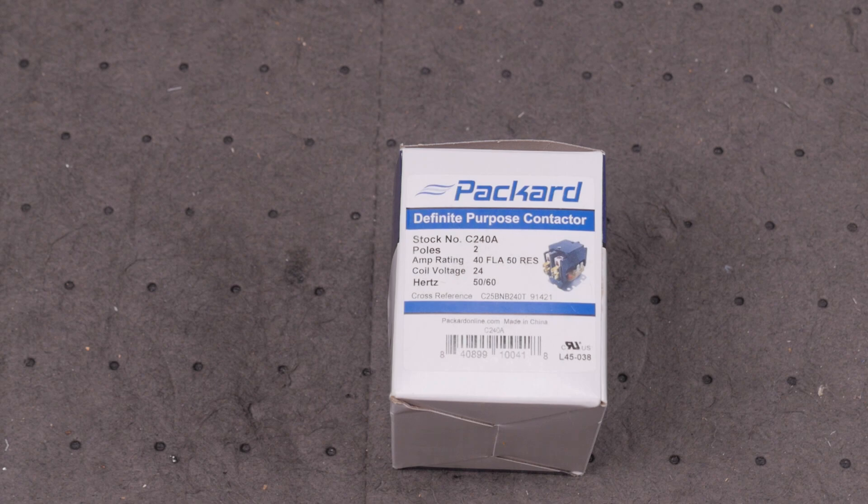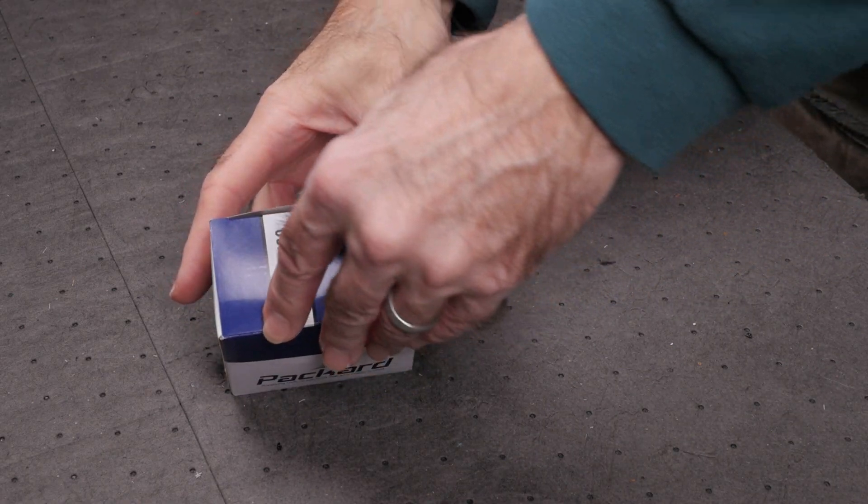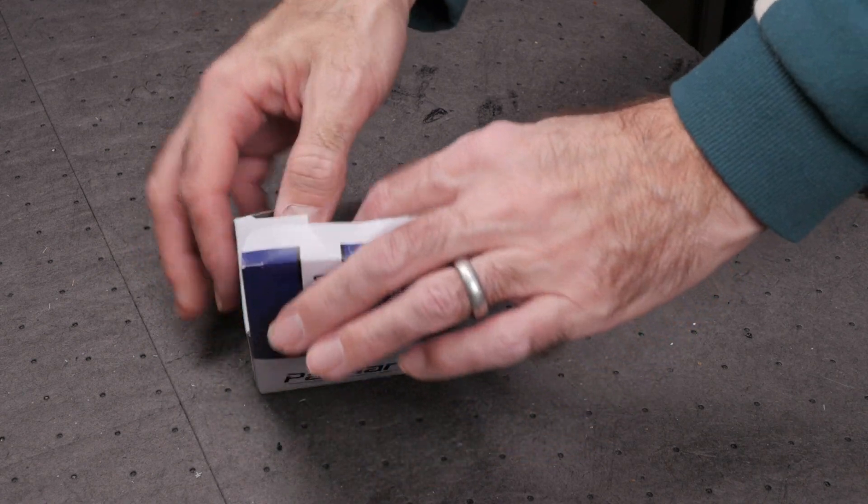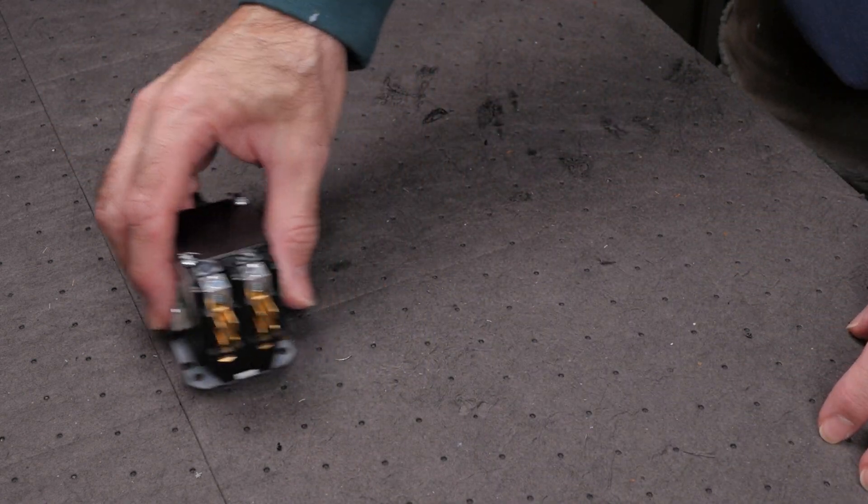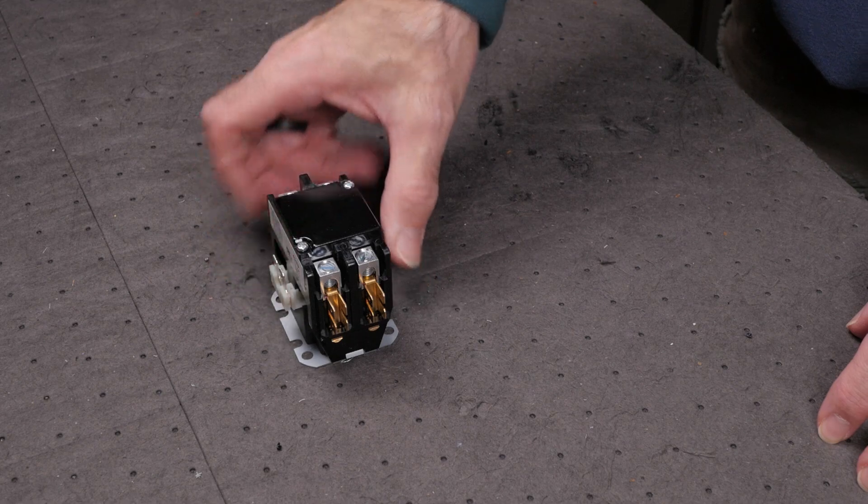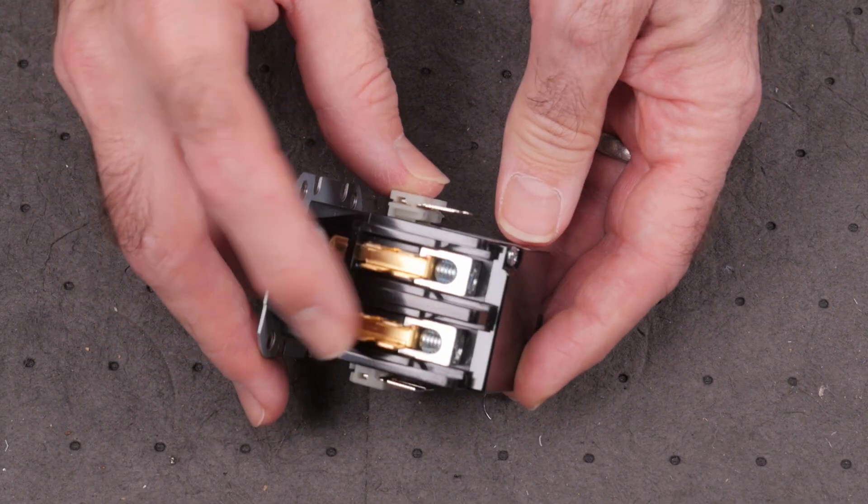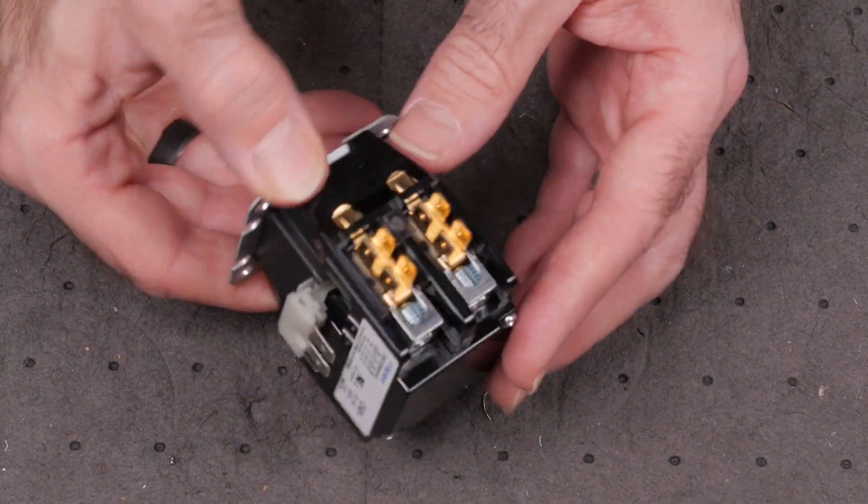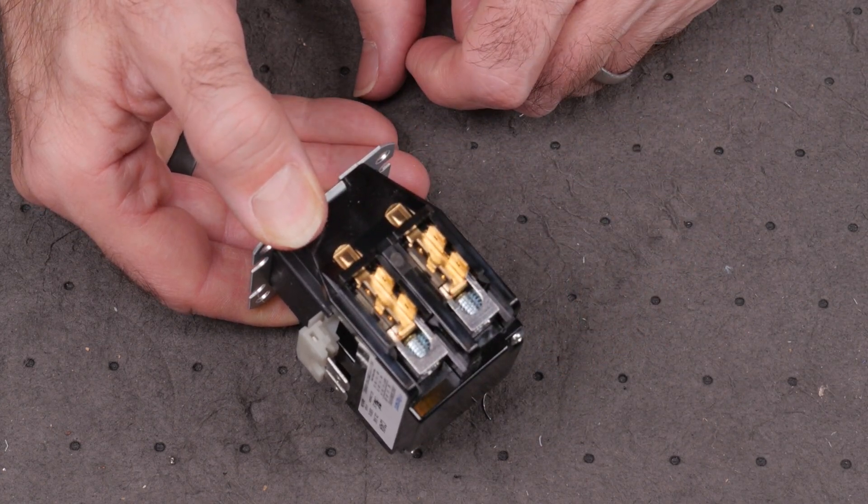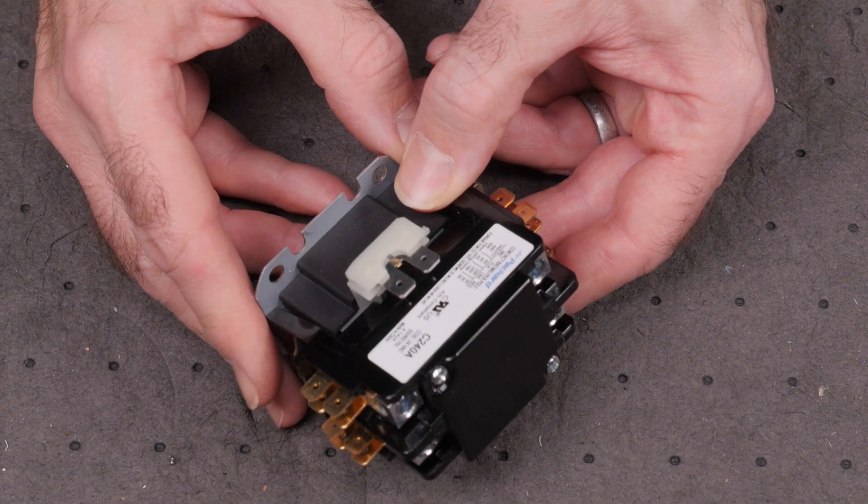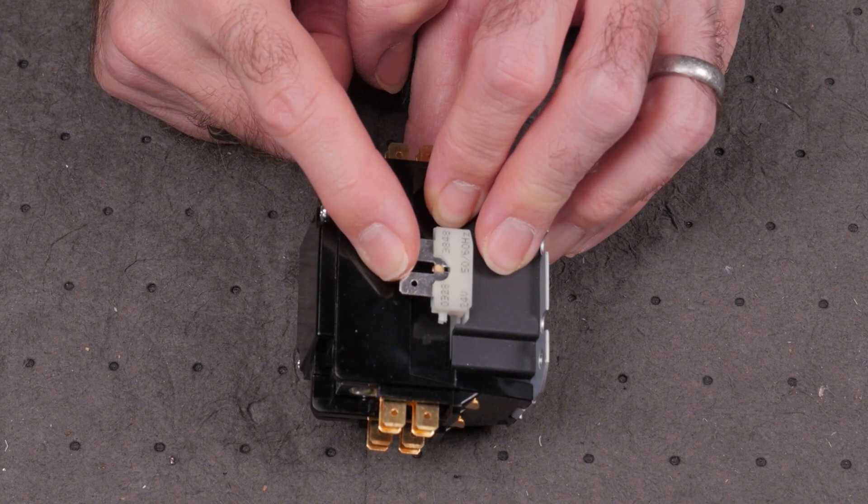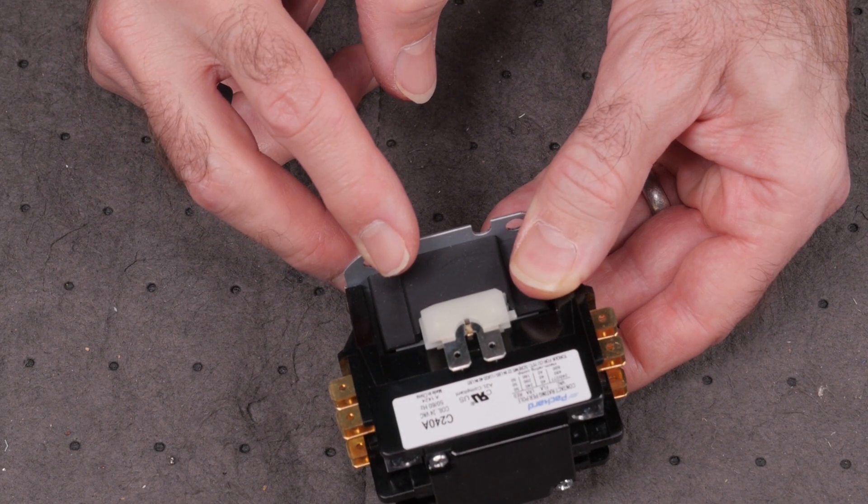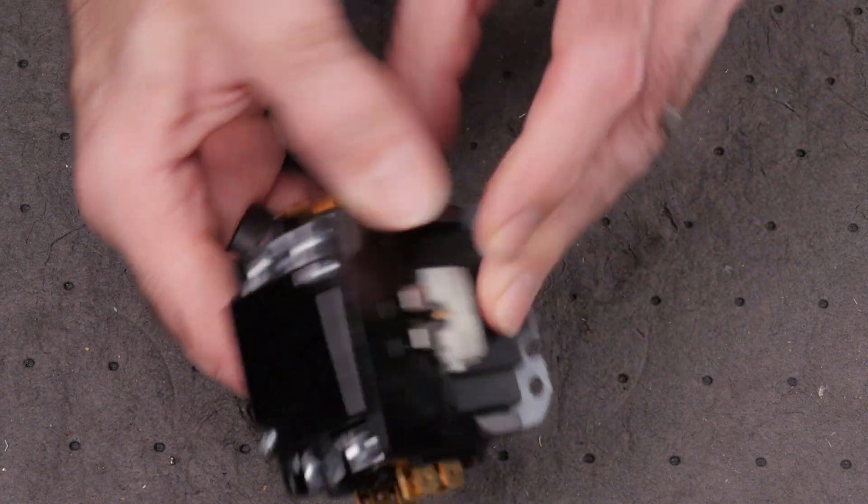A contactor is basically a switch, but instead of throwing a lever or turning a knob, we'll use the 24 volts from our transformer connected to the coil lugs to do the work when the new thermostat tells it to. These lugs are where we connect the circuit we want switched. They're normally open or disconnected until the coil is activated. These terminals are for the coil. When 24 volts is applied across the coil, the contactor closes and the circuit is completed.